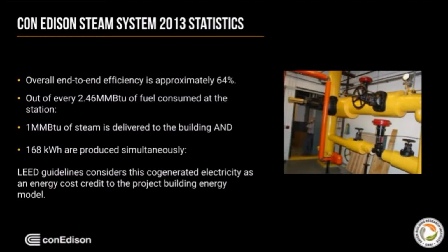Now let's quickly take a look at the back-end calculation side of this. As we've learned, the overall energy efficiency of Con Edison's steam district energy system is 64%. This translates into, per every 2.46 million BTU of fuel consumed at the station, 1 million BTU is delivered to the building, together with 168 kilowatt-hour of electricity that is produced simultaneously, as we reviewed previously. The LEED guideline considers this as energy credit in the calculation model. Let's take a look at an example.